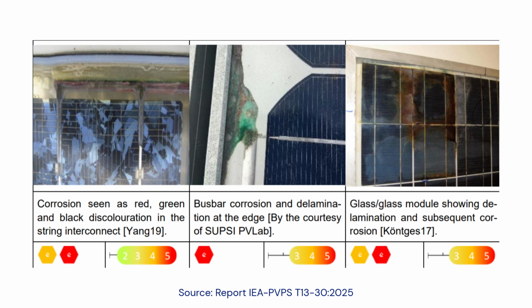Depending on the material combinations, corrosion is furthermore noticeable by the presence of galvanic products that may appear powdery, white, light gray, and have a yellow, blue, or green tinge. The defect occurs typically at the solder bonds, on the cell gridlines and fingers or the cell and string interconnect ribbons. It is very often observed together with other failures like delamination and discoloration of the encapsulant and sometimes with burn marks. Under certain circumstances, corrosion is more visible near cell edges.